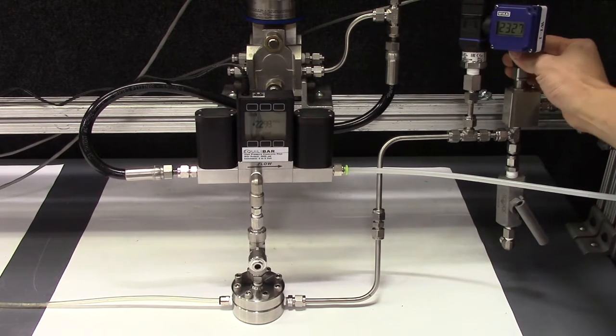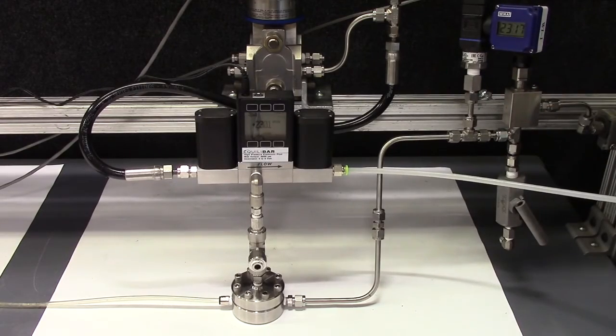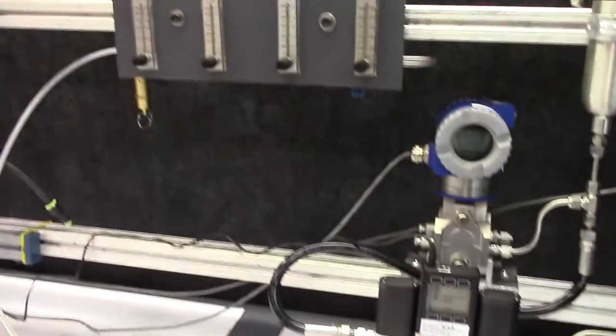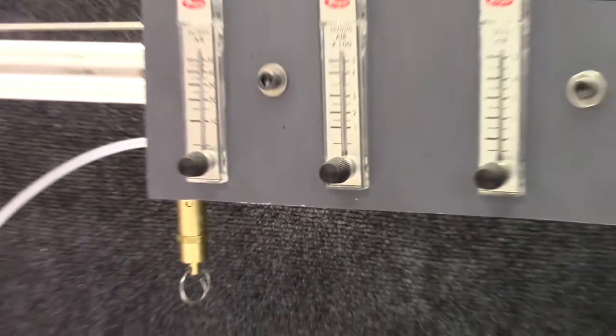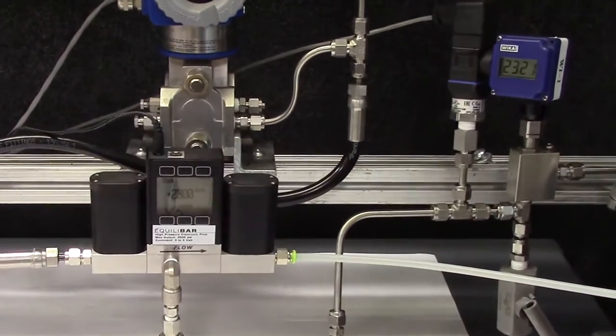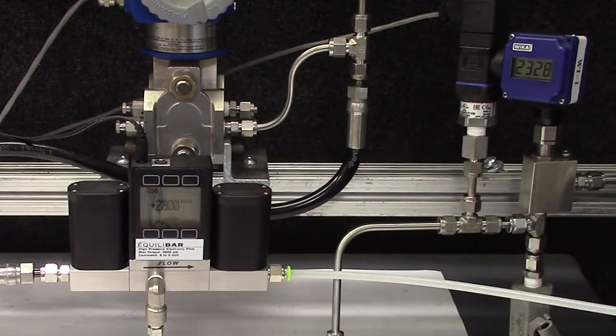So first, I will just shut this needle valve all the way off. And you can see that the flow rate has dropped and is now at zero flow. The pilot and the inlet pressure are remaining stable at 2300.